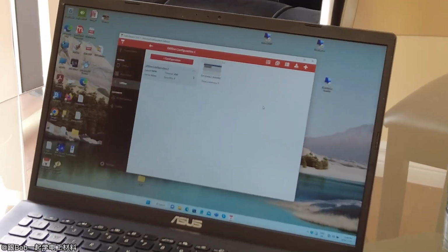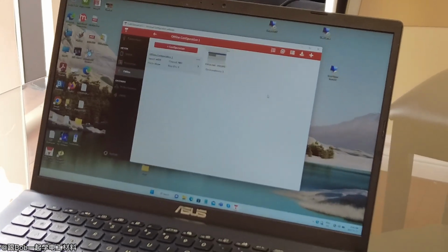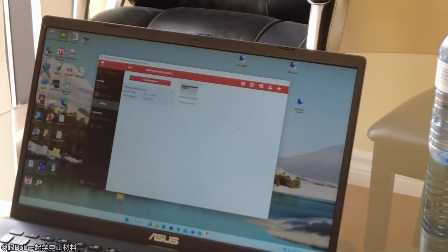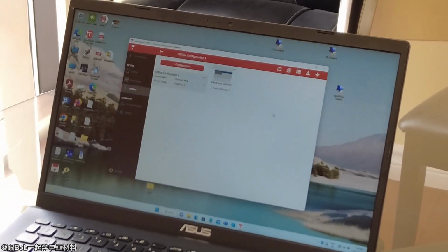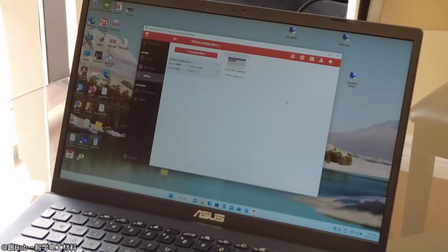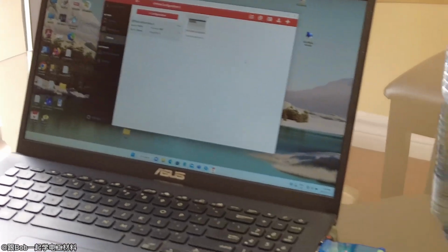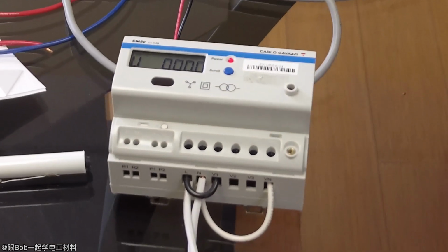I explained to them we can use this later, because normally we buy from Leviton. It's like a big cabinet inside. You have to put 10 to 12 sub-meters, it's a different sort of thing. So this one here, you can get this Measurement Canada sealed. So if you're doing it for billing, we can supply this with a sealed meter. And then if they already have billing software, they could probably import this into that system as well, because it uses Modbus, and that's pretty common.